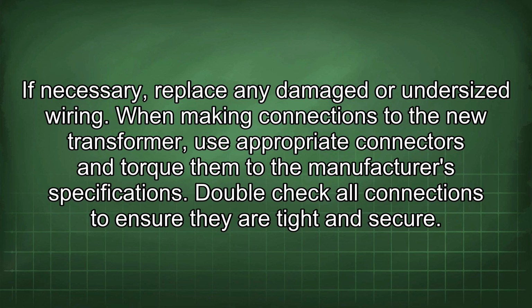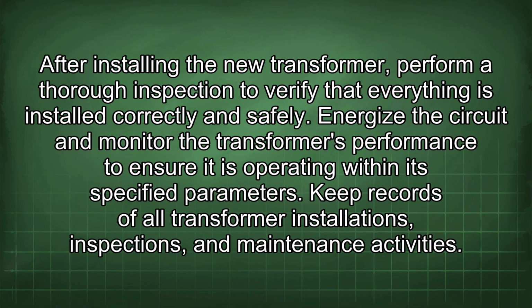If necessary, replace any damaged or undersized wiring. When making connections to the new transformer, use appropriate connectors and torque them to the manufacturer's specifications. Double-check all connections to ensure they are tight and secure. After installing the new transformer, perform a thorough inspection to verify that everything is installed correctly and safely. Energize the circuit and monitor the transformer's performance to ensure it is operating within its specified parameters.